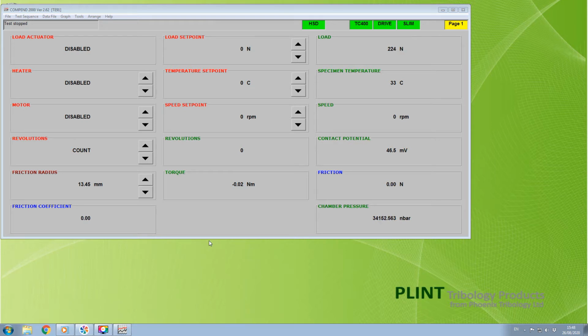If a peripheral device box on the status bar turns from green to white, this indicates a loss of two-way software communications between the front end and the device. If the box turns red, this indicates a hardware fault with the comms port or the associated interconnecting cables. All peripheral device boxes must be green for satisfactory operation of the machine.